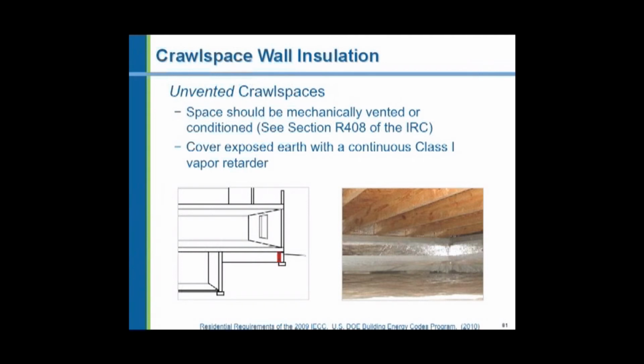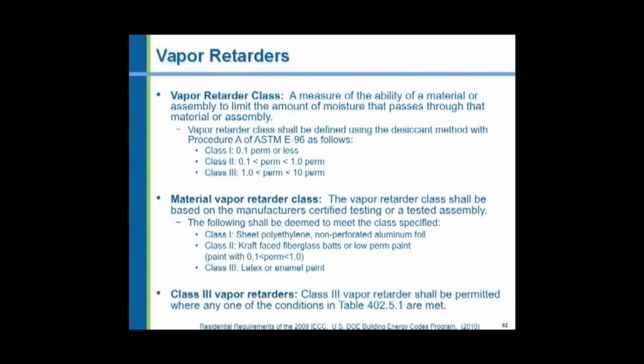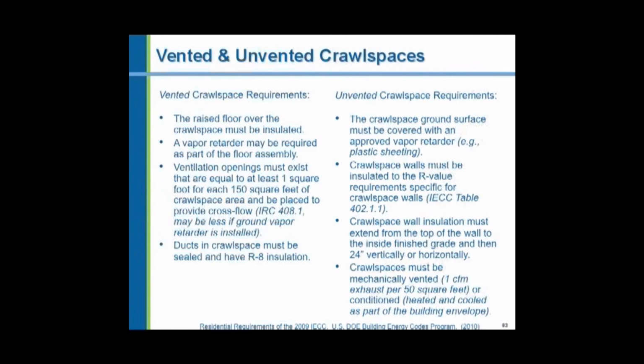And also, if you put a horizontal furnace in the crawl space, you have to somehow protect this vapor barrier. People are going to be down servicing that furnace. They're going to be changing filters, working on the temperature controls. You have to protect that vapor barrier from being damaged. In this case, think about installing a lightweight concrete floor, only a couple inches thick. They call it a mud mat, in the area where you come down through the access opening and over to and around the furnace at the very least. The vapor retarder has to be a class 1, as it says, 1/10 of a perm or less, and this basically means a 6 mil polyethylene or thicker. And here's the requirement for ventilating the crawl space, as we mentioned earlier.